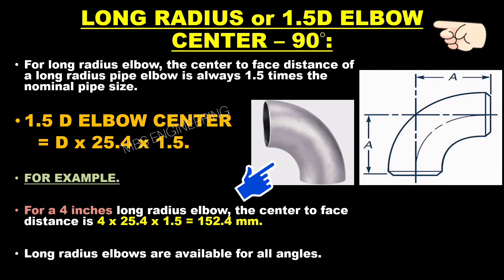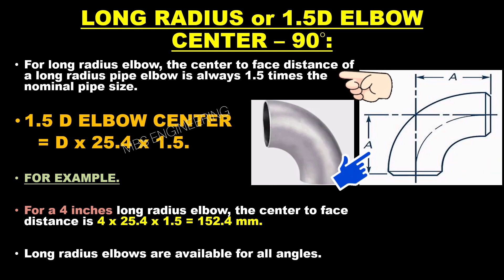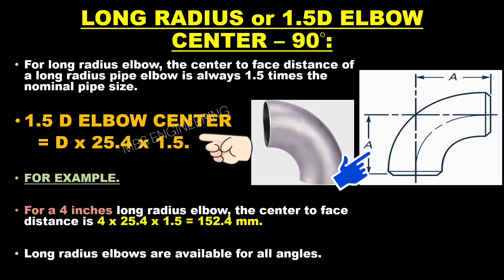Next, we will calculate the elbow pipe center for long radius or 1.5D at 90 degrees. The center-to-end dimension is the length of the elbow measured from the center of its radius to the end of either opening — refer to the accompanying images where dimension 'A' indicates the elbow center. For a long radius elbow, the center-to-face distance is always 1.5 times the nominal pipe size.